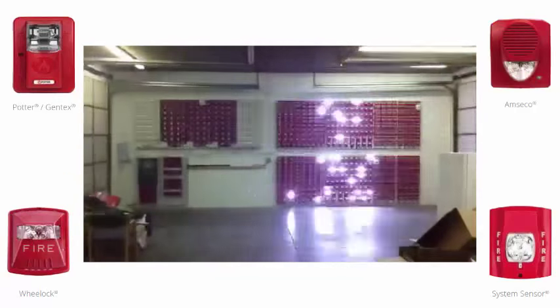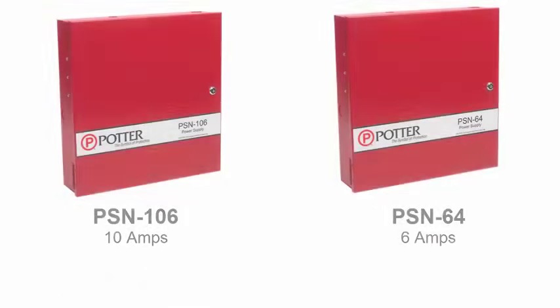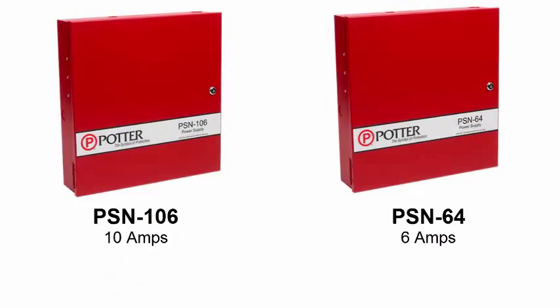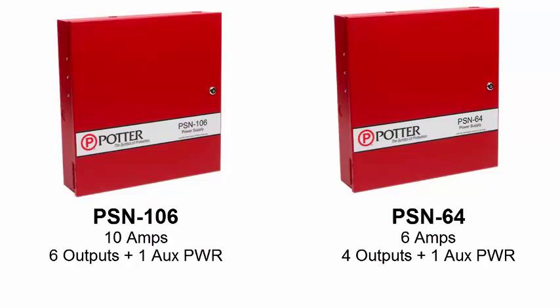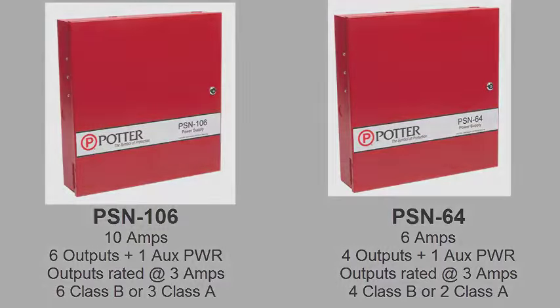By the end of this video, all those strobes will be synchronized using this PSN series power supply. The PSN series notification power supply comes in two sizes, either a 10 amp or a 6 amp. The 10 amp has 6 outputs while the 6 amp has 4 outputs. Each panel also has one aux power circuit. All the outputs are each rated at 3 amps. Both panels can be wired class A if necessary.